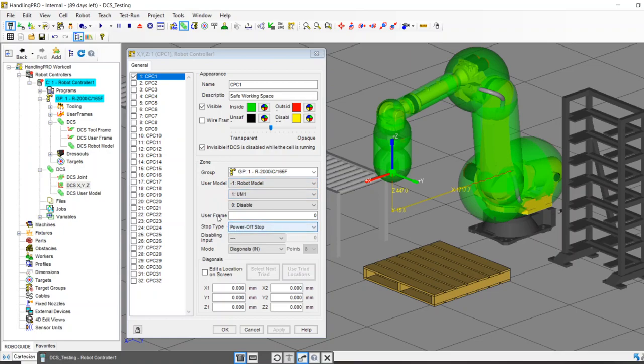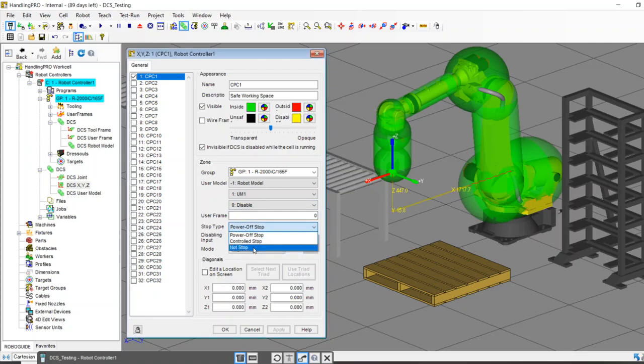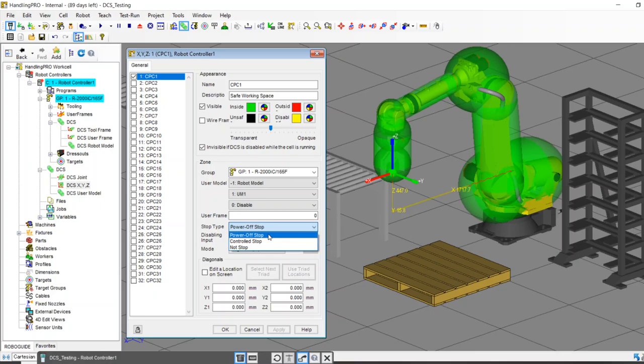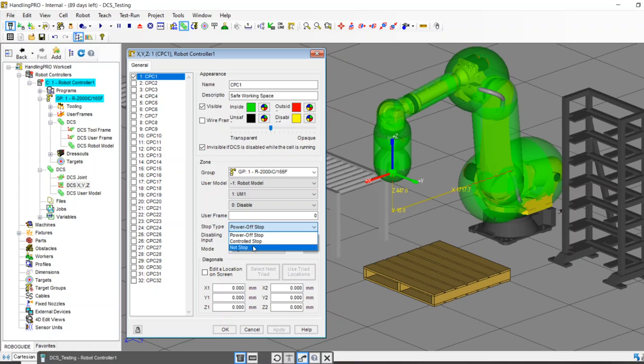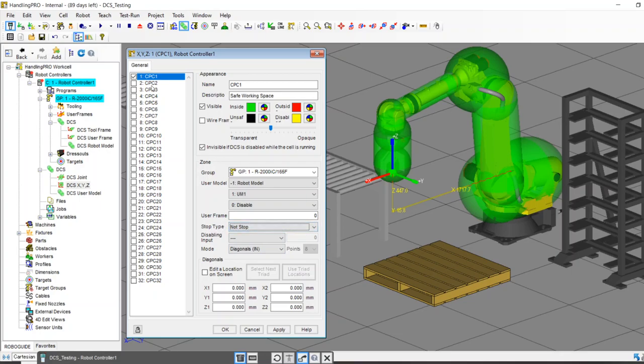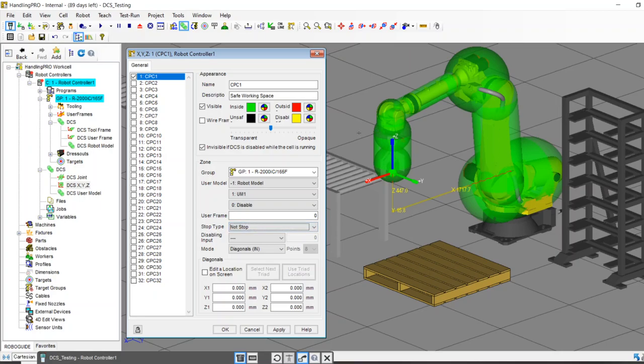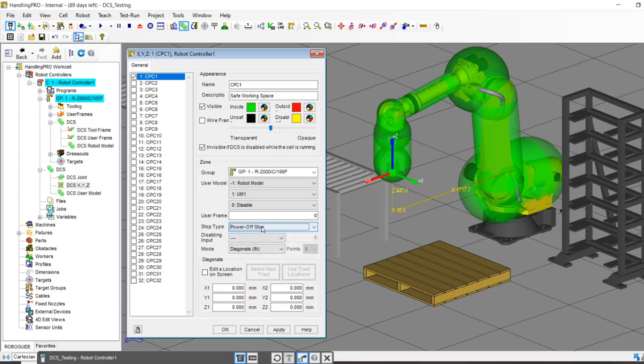Let's look at the stop type. There's three ways to handle a breach of a CPC. You can either e-stop the robot, which is a power off. So safety rated, it's just like hitting the e-stop. There's also a controlled stop, which is equivalent of hitting the hold button or pause button. The robot will use the servos to decelerate and come to a controlled stop. Or you can do a not stop. Sometimes people build CPCs just to know where the robot is. If you set this up as a not stop, then we can take the CPC output and use that as a digital output to a PLC, to an HMI, to a conveyor, whatever. And just let ancillary equipment know, hey, the robot's on the left side, the robot's on the right side, whatever it's doing. For here and now, I'm going to consider it a safety rated e-stop.